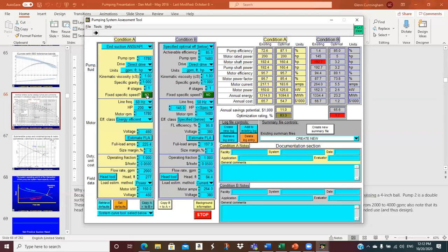But it's probably more conservative to leave that on yes and accept a lower optimal efficiency, which you can be pretty darn sure is the same type of pump. If you wanted to replace one, if this thing was old and falling apart, then you could buy one with, you know, 85% efficiency, put it in there, and you can include those savings in your calculations. So that's kind of what that is.